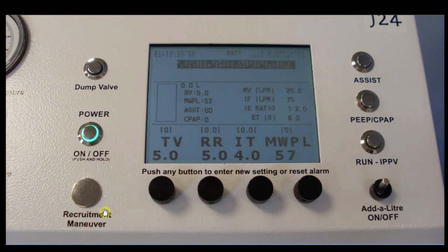At the moment we don't have a simple recruitment maneuver, so this button is a blank. Up here we have the assist button that we've seen to set the assist value, the PEEP and CPAP button, and here is the run or IPPV button. To change from spontaneous breathing to ventilation, simply press this button. This will illuminate and the machine will go into the IPPV mode. Press it again, the light will go out and the machine will go back to the spontaneous mode. There is no need to make any other changes to change between spontaneous mode and ventilation mode.